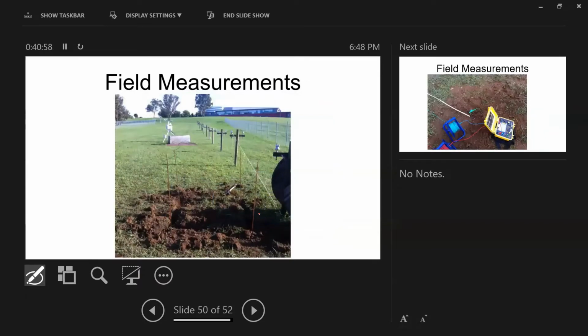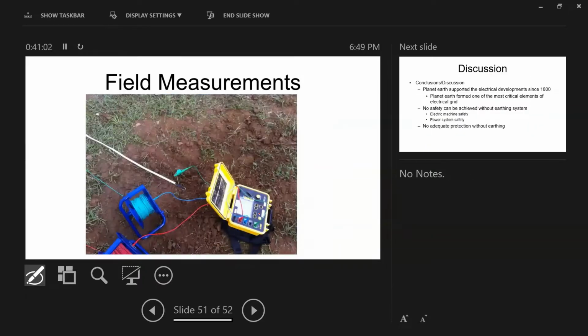earthing system. And we bought an AEMC unit, an accredited unit, and we inject current and measure along the line. If you take it deep into the ground, what will happen along the way? On a rainy day and a very dry day, we tested and got massive results. That's why this experiment managed to publish about 25 journals, not only on this, but also on AC interference, soil resistivity, fault potential, all this information.